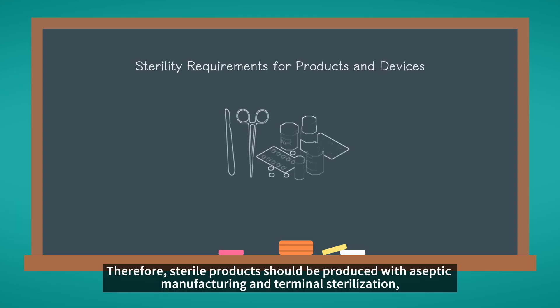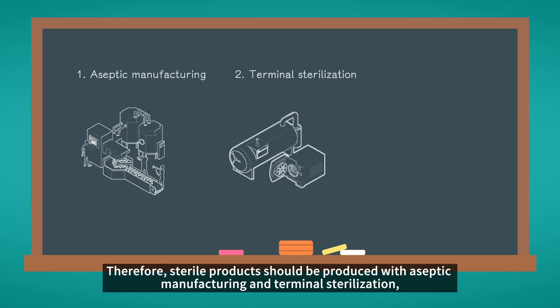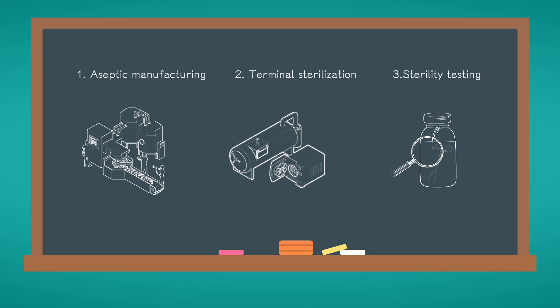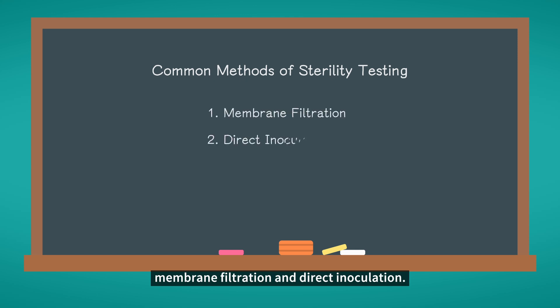Therefore, sterile products should be produced with aseptic manufacturing and terminal sterilization, followed by sterility testing to ensure that no viable microorganisms are present in the product. Common sterility testing methods are membrane filtration and direct inoculation.